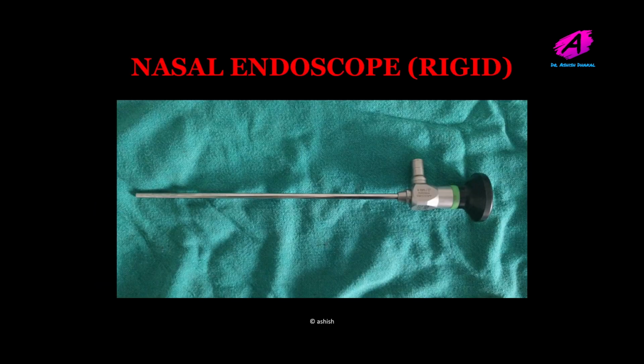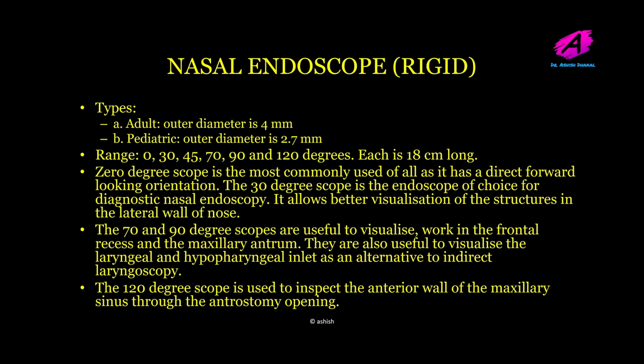Nasal endoscope, rigid. Rigid nasal endoscopes are adult or pediatric ones. According to diameter, the adult one is 4 mm in diameter, whereas for pediatric, the outer diameter is 2.7 mm. The range is 0, 30, 45, 70, 90 and 120 degrees, and it is 18 cm long.